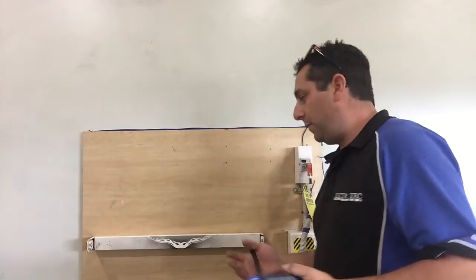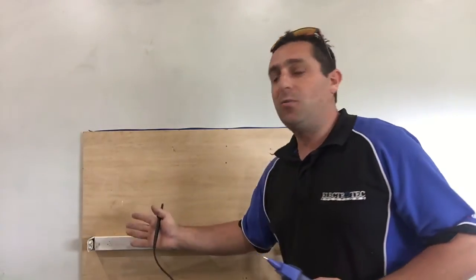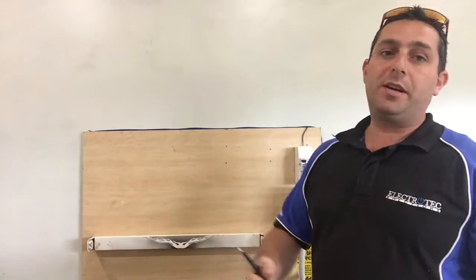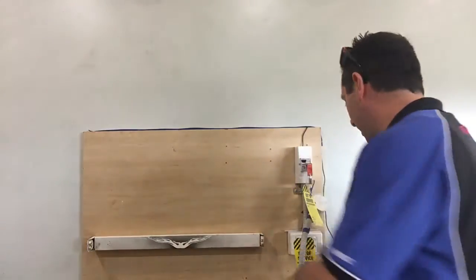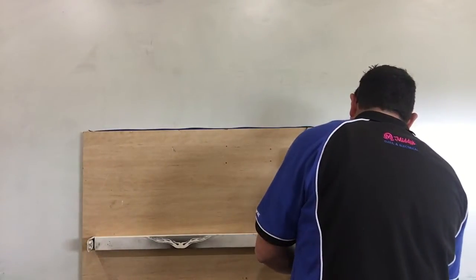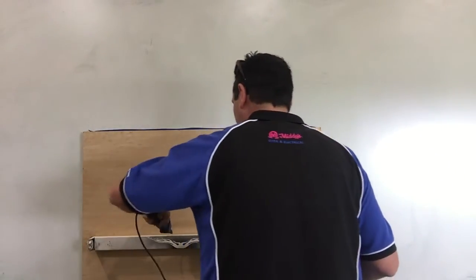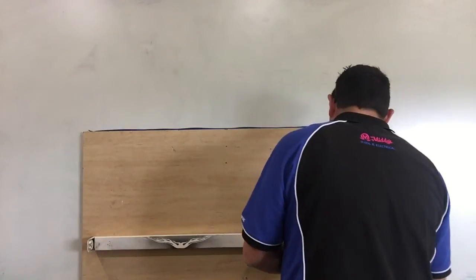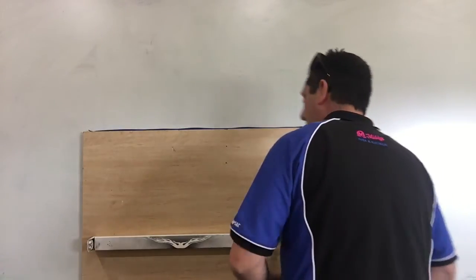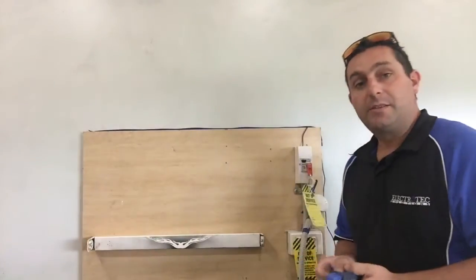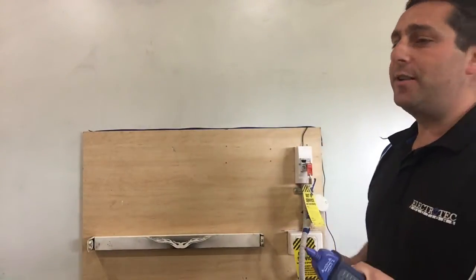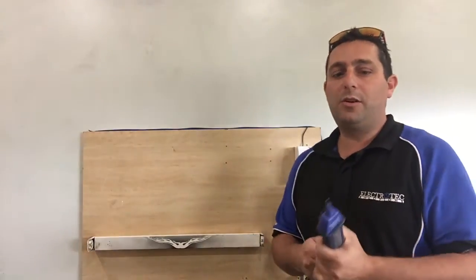What happens if we've screwed this back to the wall? There's a cable behind it. We've drilled into an active. We've screwed into it, and now the frame's live. So I think it's important to test our tester, test our frame again, retest our tester, and we can really definitely 100% establish that there's no stray voltages. Now that's not necessarily in the exam, but it's something that I like to do.